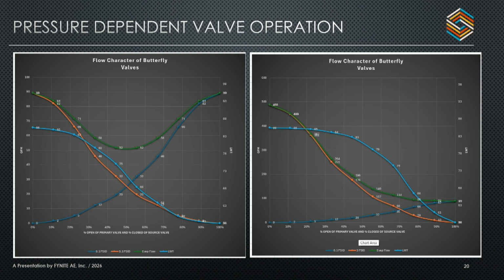And if you exacerbate that, say 3 PSI versus 0.1 PSI. So if your hot water header to net water header is at 3 PSI differential, and your chilled water to net water is at 0.01, you could have up to a 400 GPM decrease on the flow, which would definitely trip out any system. Now this relationship is inverted if the pressure differential is the opposite way. If your net water is elevated above either header, then you'll end up with a flow increase on your evaporator.